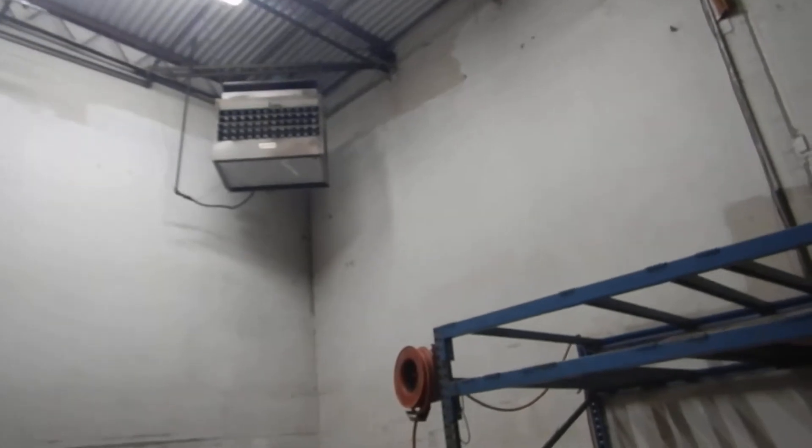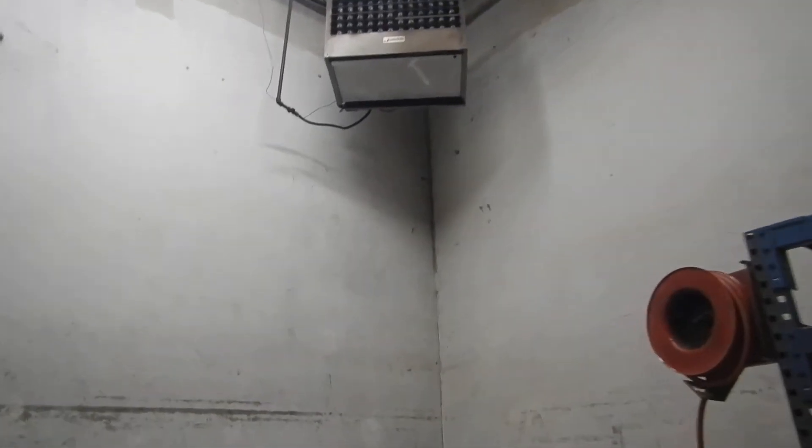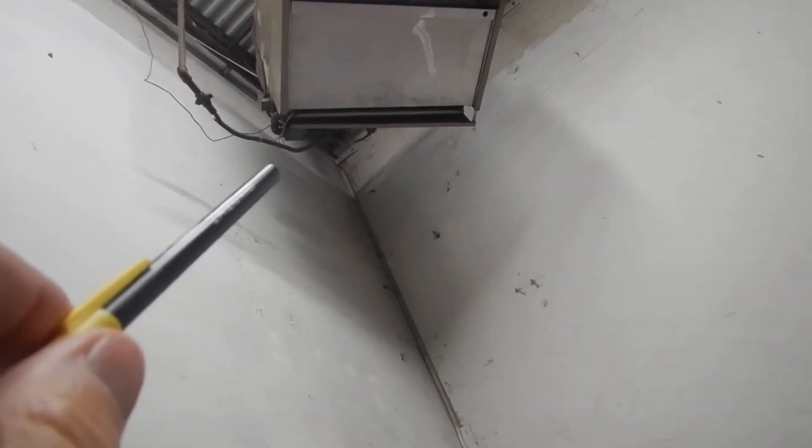Pretty much what's original has been hanging up there for a while. This connector — it's a brass connector, it's an obsolete gas connector — going to the furnace. And we do not have a sediment trap for the gas piping.